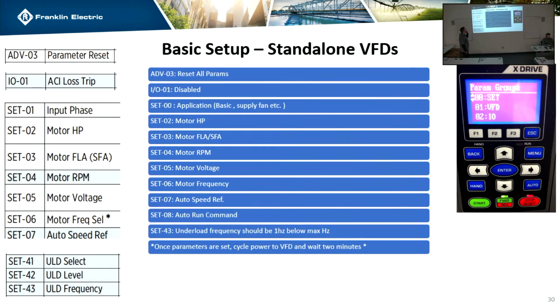So this is just kind of walking through a basic setup. Even though the drive has hundreds of different things you could do, it's really 10 or 20 things that you're going to be sticking to. You're always going to set 0, 0. Almost anytime you get a drive from us in a panel, it's going to be set to basic. The other ones, supply fan, all that stuff, are great for the drive by itself, but we use a lot of relay logic, so we just set the drive up in basic, and we know how we want the drive to work. But if you have a drive by itself, basically all the quick start ones are going to default your acceleration time and protections and things like that for the industry standards of whatever you're setting up. You're always going to have to do set 0, 0.